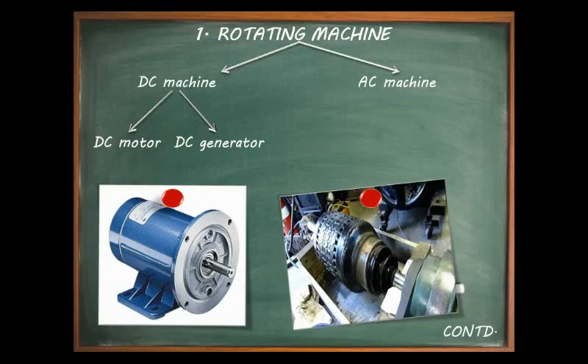A generator is usually kept in a suitable position, handled by technical persons, so mechanical protection for coils and armature can be reduced to a minimum, which also facilitates cooling, inspection, and repair. On the other hand, motors work in conditions of dampness, dirt, inflammable gases, chemical fumes, and liability to mechanical damage, so protection must be adequate. That is why the frames of DC motors are made flame-proof, semi-enclosed, or fully enclosed.